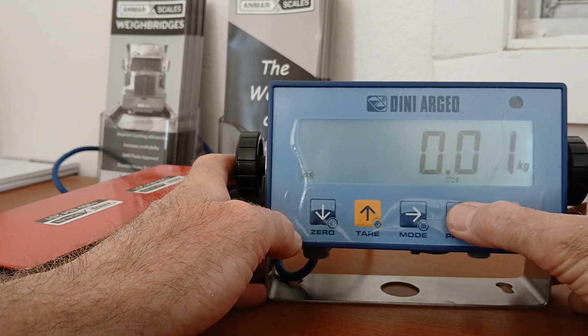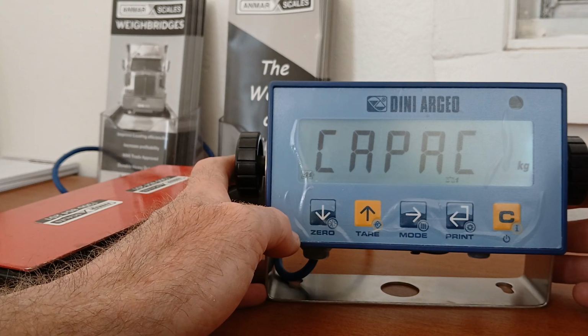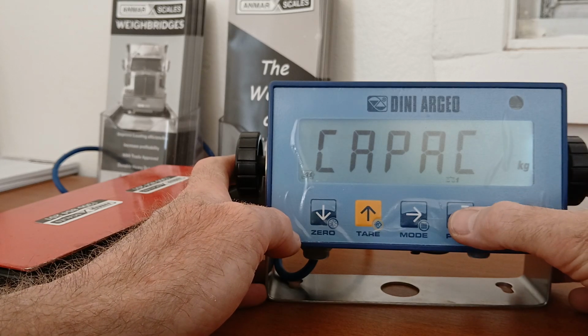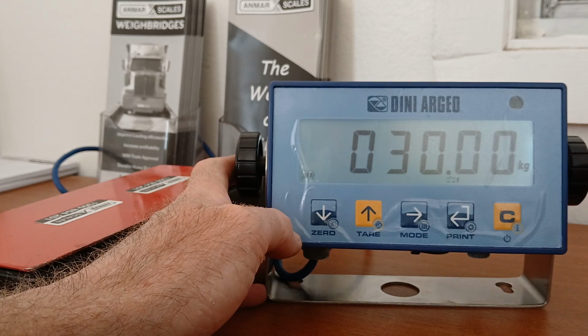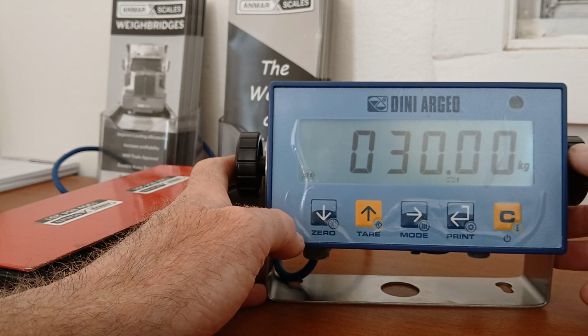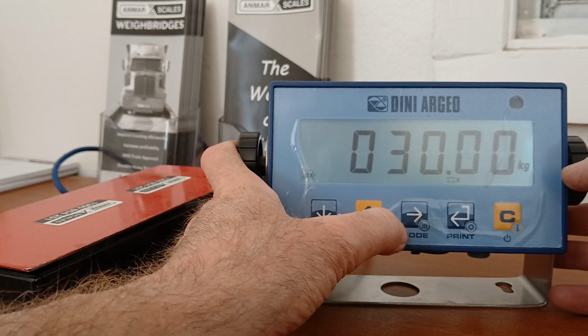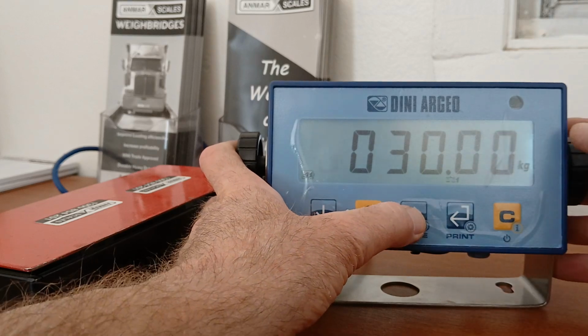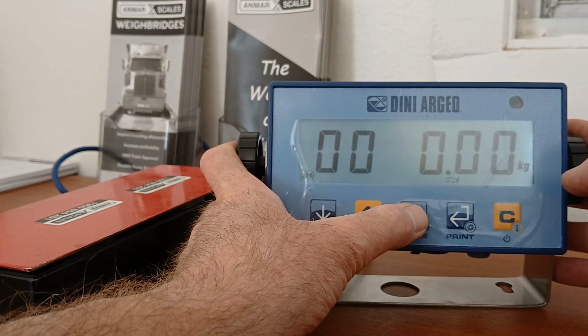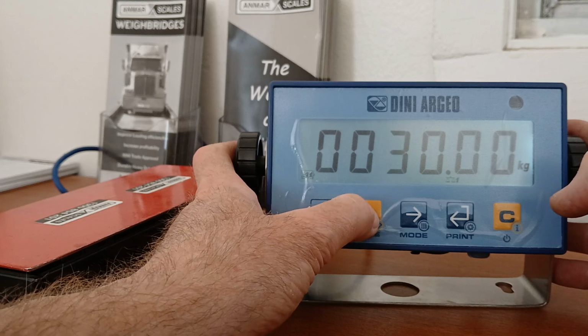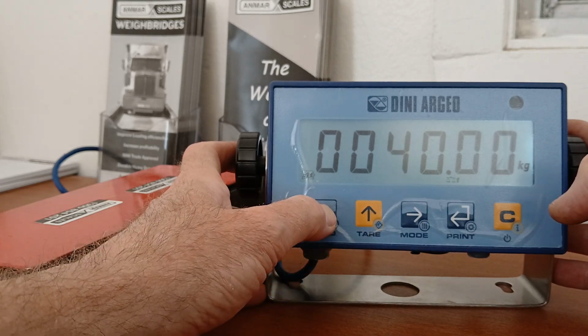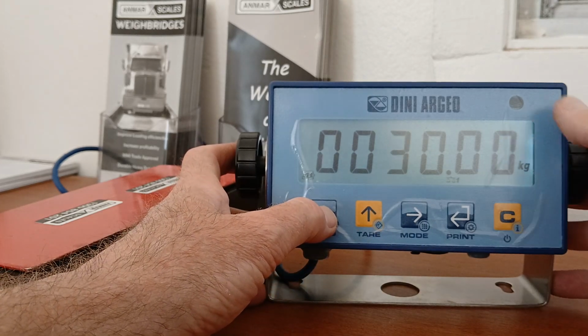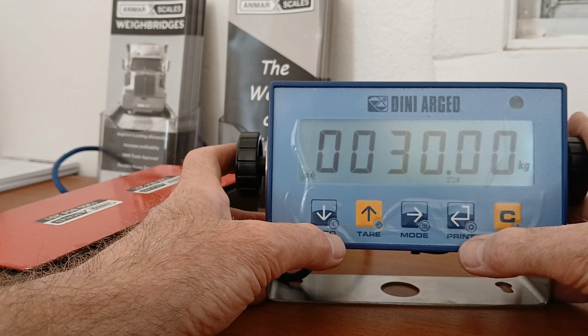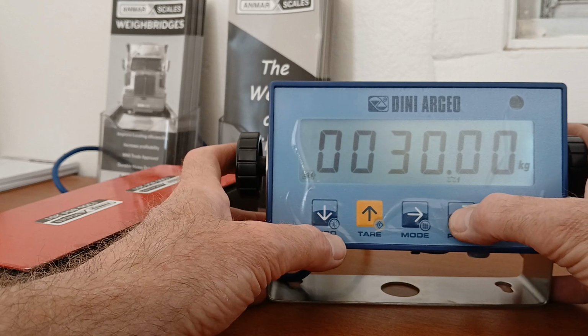We push enter, then it displays capacity. That is the maximum capacity that we'll be weighing on the scale. This one's already set to 30, so that's good. If we want to change it, we just shift the flashing arrow using the side arrow button, and then up and down arrow to change the capacity accordingly. Once we're happy that we have what we require, we push the enter button again.